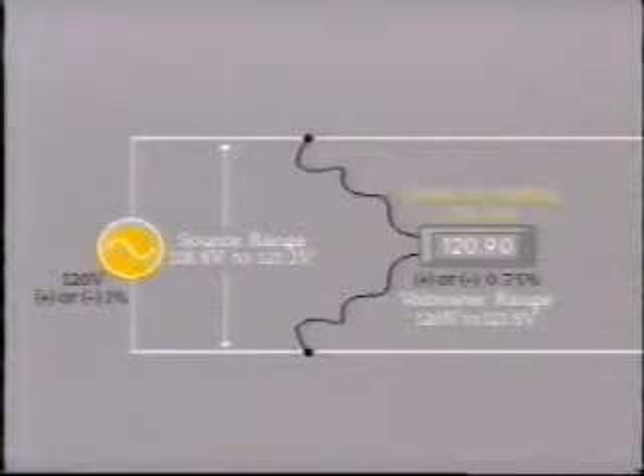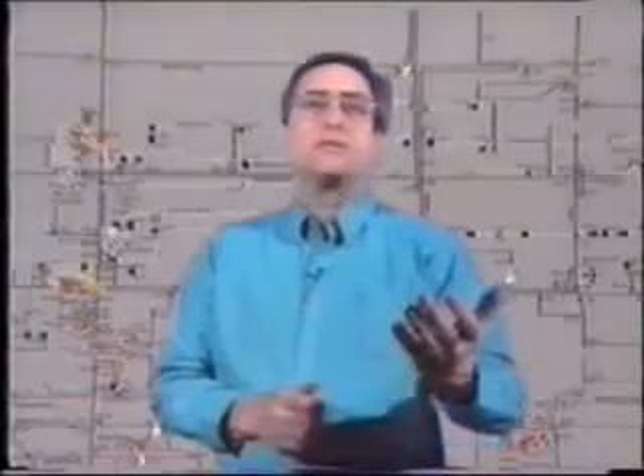However, it could be that the voltmeter is actually reading 0.75% low, in which case the actual measured source voltage would be 121.8 volts, outside of its specified limits. This example shows a worst case, which is not likely to occur in practice, but it does serve to illustrate the meaning and importance of instrument accuracy.